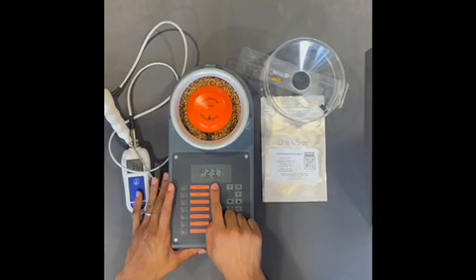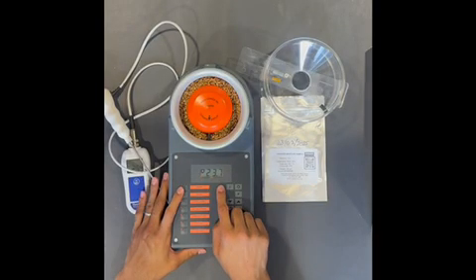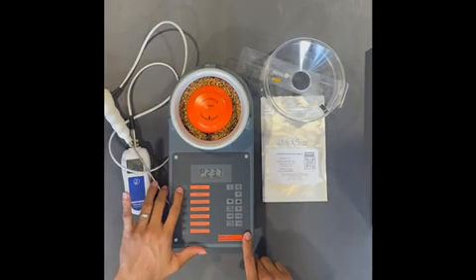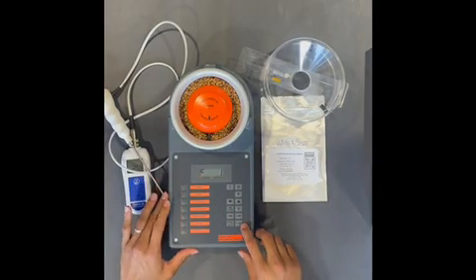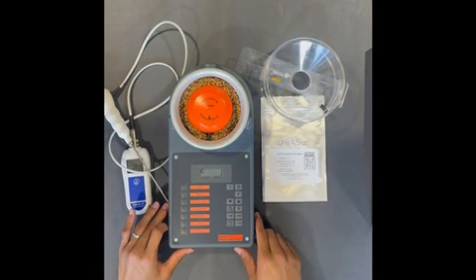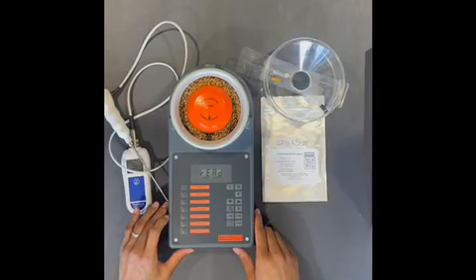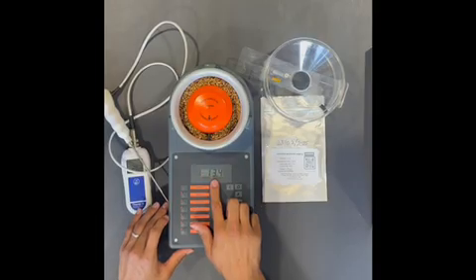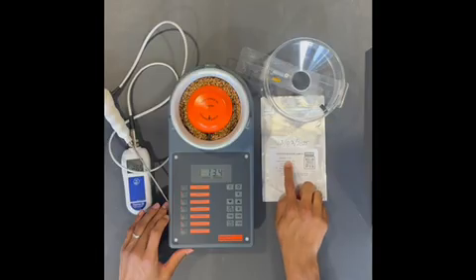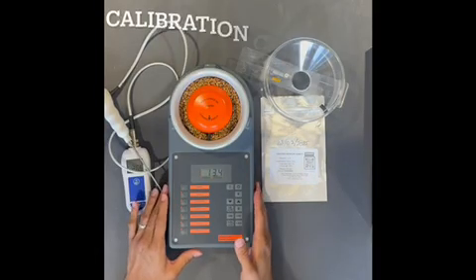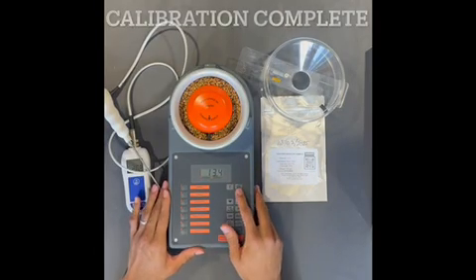It comes to 23.7, which was the settled value when we checked the grain. We then want to go ahead and press 1 for wheat and H2O, which gives us the moisture level that's on the bag, which is 13.4. So your calibration is done and the machine is ready to use as normal.